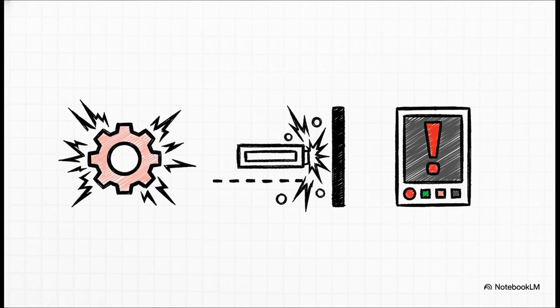The service manual points to three classic red flags. First up, jerky, stuttering movements when you're expecting a nice, smooth glide. Second, an axis that just slams to a hard stop after a rapid move. Ouch. And finally, the machine just keeps throwing excessive error codes at you. If you're seeing any of these, you are almost certainly looking at a counterbalance issue.